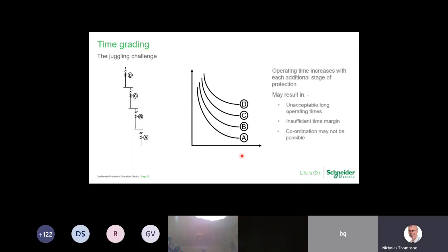So what we've got there, we've got the dangers. So we've got to have a safety margin between each curve to allow for overshoot or allow for errors. We may end up with a case that I've said just a minute ago, where we don't have that amount of time margin, and it can become impossible to do any good coordination between our different circuit breakers.